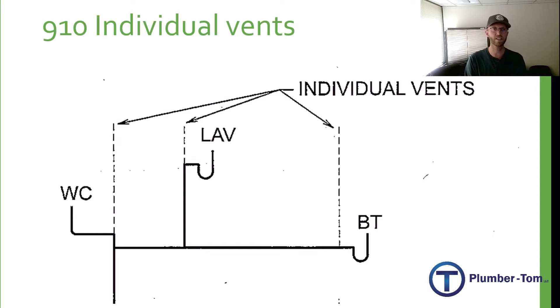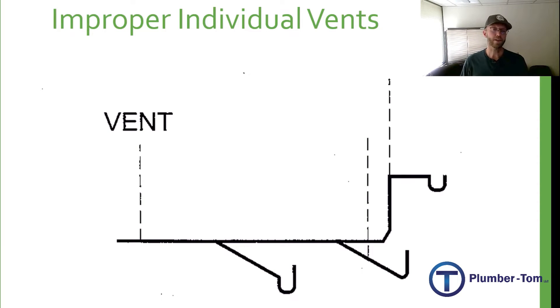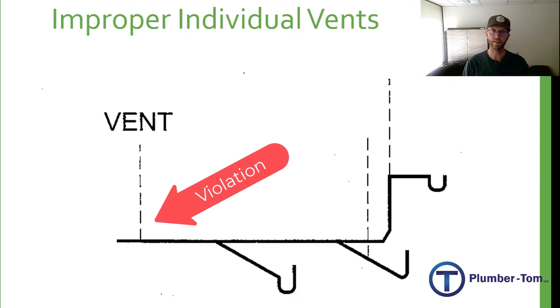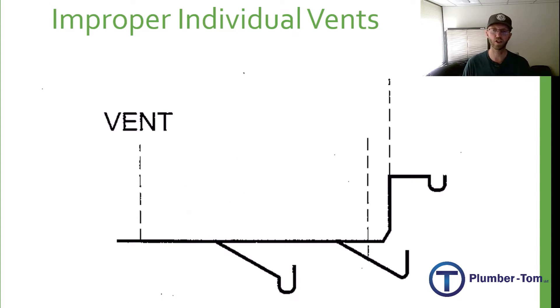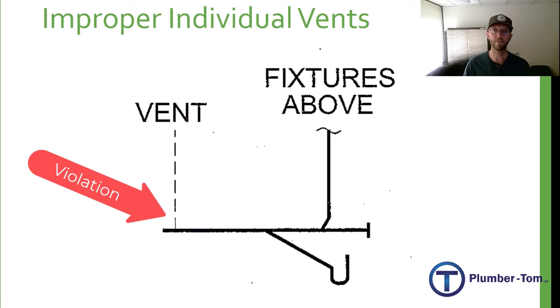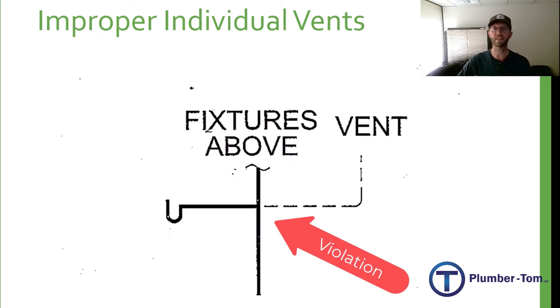As we look at some of our other options, have a look at a few improper individual vents. On the right we have a couple that are done correctly, but in the middle we have a floor drain coming off and the vent is not connected directly to that trap arm. The drain that comes over to the trap is where that vent should be connected, not downstream on the horizontal branch. Here's another similar example: we have the trap arm coming off of the horizontal branch, but there are also fixtures from a stack above. That vent is downstream and not connected directly to the arm of the trap, and therefore it is not venting properly for an individual vent.